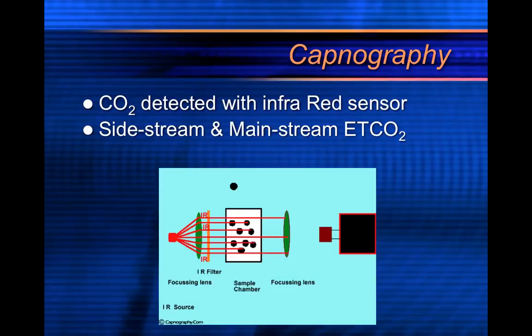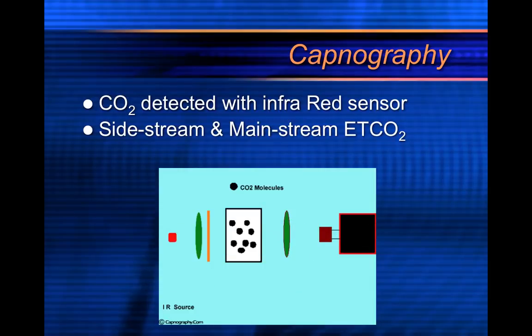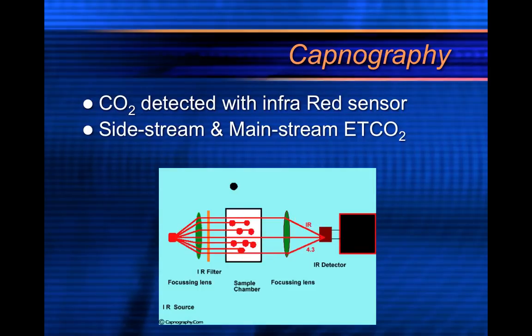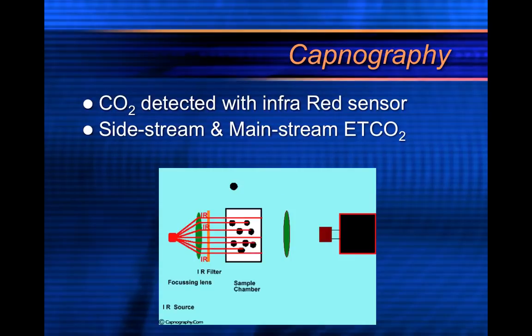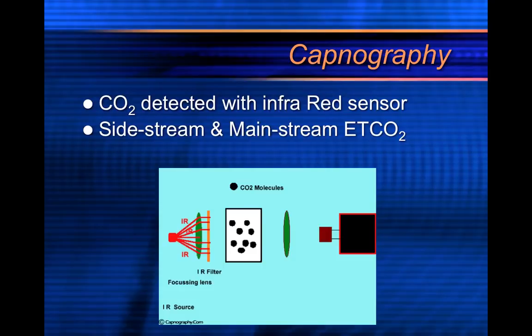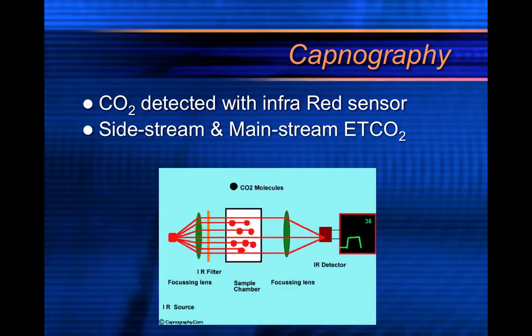CO2 is detected with infrared sensors, and there are two different kinds: sidestream and mainstream. Mainstream CO2 gives you the sampling of CO2 right at the device — for example, if you have a device attached directly to an endotracheal tube, giving you the reading right there at the ET tube, that's mainstream. Sidestream takes a sample through a thin tube all the way back to a monitor. The Zoll, LifePak, and Philips monitors all use sidestream, where a sample is taken back to the monitor and an infrared light at that monitor reads the end tidal CO2 value.